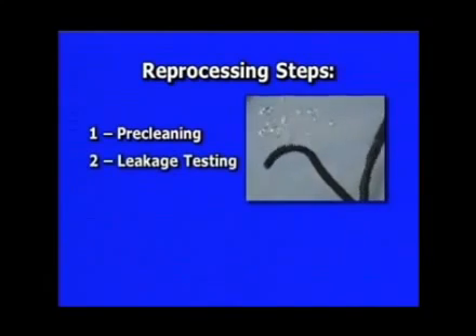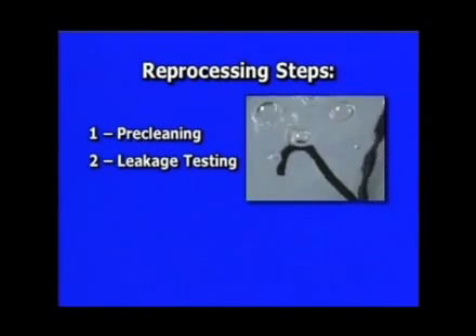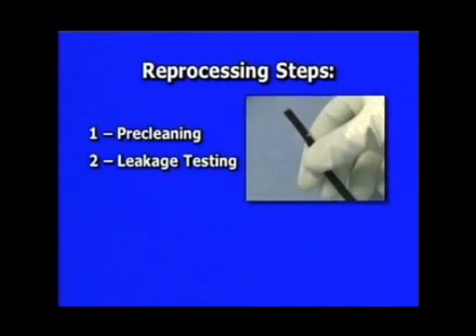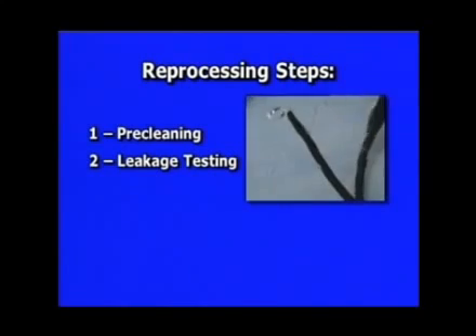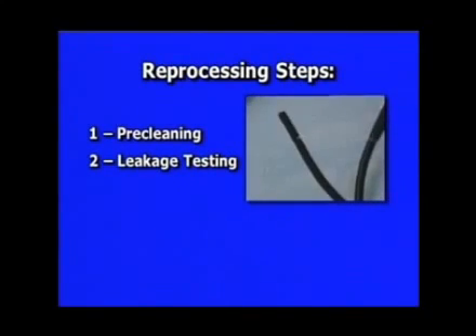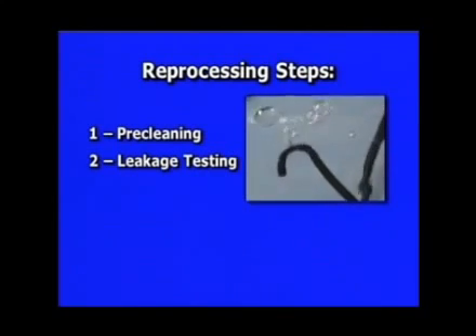2. Leakage testing is required to ensure that the channels and insertion tube are not damaged and that all seals are air and watertight. Routine leakage testing prevents costly fluid invasion and therefore costly instrument repairs. Never use a bronchoscope that has a known leak on a patient, as this can be an infection control risk.